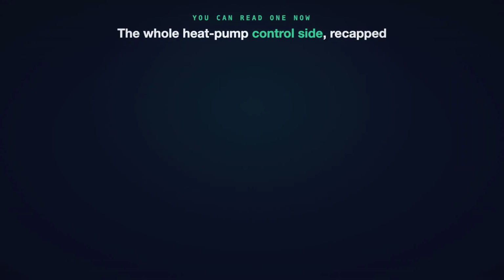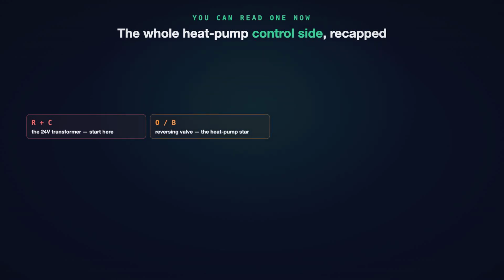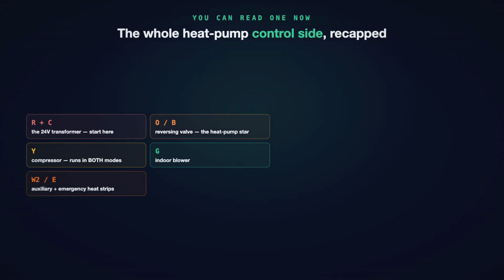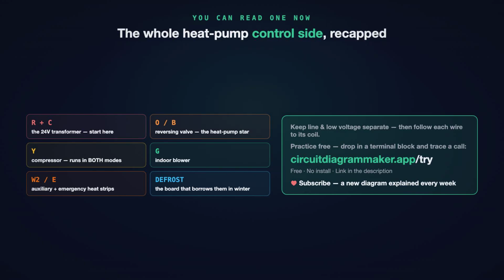So that is how to read a heat pump wiring diagram. Start at the transformer, R and C. Then the extras that make it a heat pump. O or B for the reversing valve, Y for the compressor that runs in both modes, G for the blower, W2 and E for backup heat, and a defrost board that borrows them all in winter. Keep the line voltage and low voltage worlds separate, and follow each wire from the thermostat out to its coil.